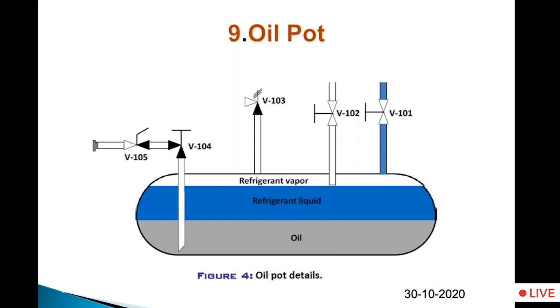Instead of that, provide a single oil pot in the entire plant room where all the oil is collected from various points. Don't drain the oil from each point. Provide a pipeline and take it into an oil pot so that all oil is collected into the oil pot, and you can then drain the oil from the oil pot.